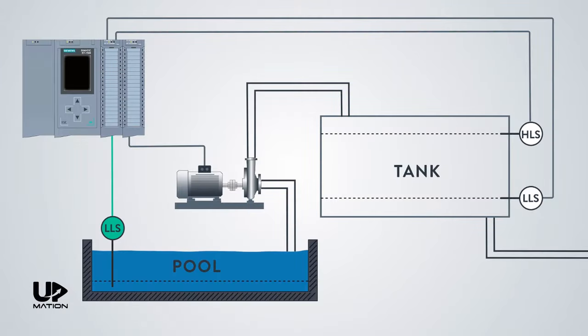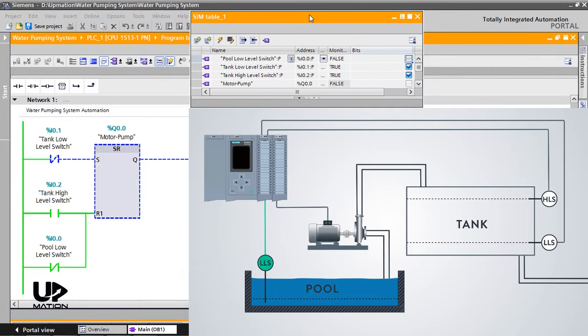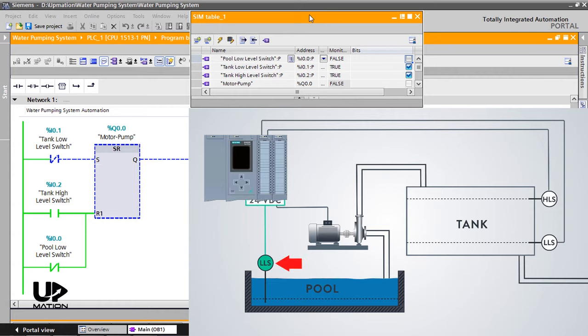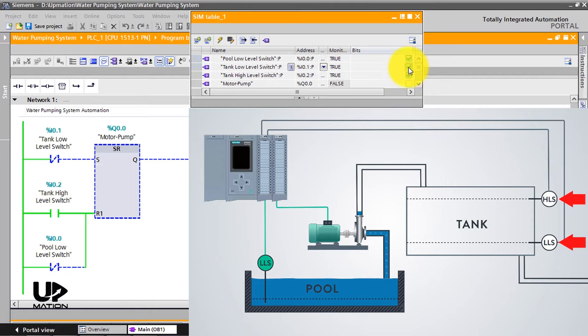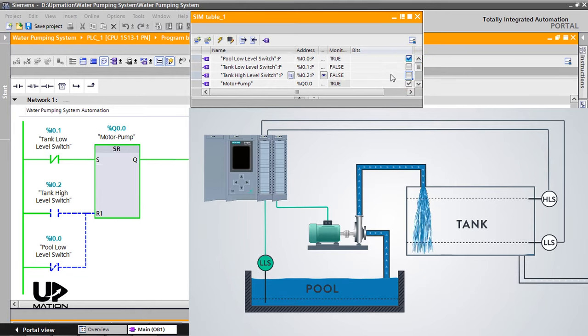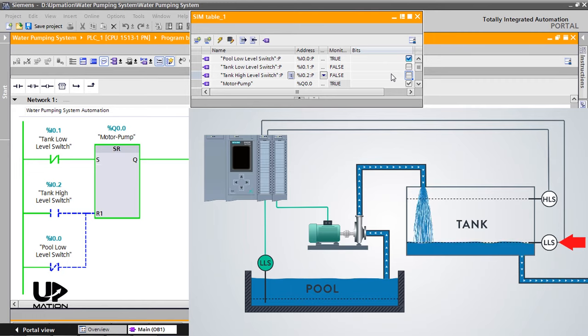Let's start with this condition. The pool is full of water and therefore the pool low-level switch is active and sending a 24V or a true signal to the PLC. The tank is empty and both the tank low-level switch and high-level switch are inactive and therefore the pump is working to increase the level of the water within the tank. Very soon the tank low-level switch becomes active as it senses the water.